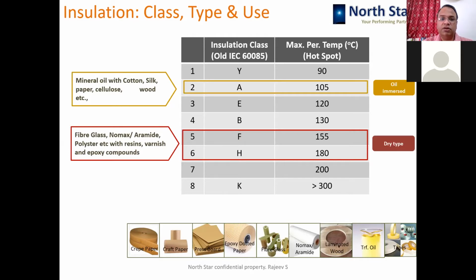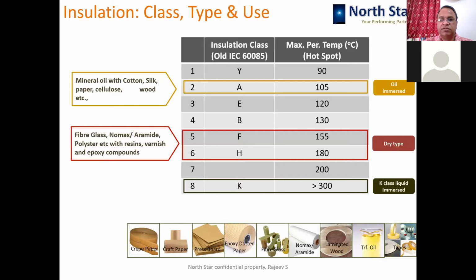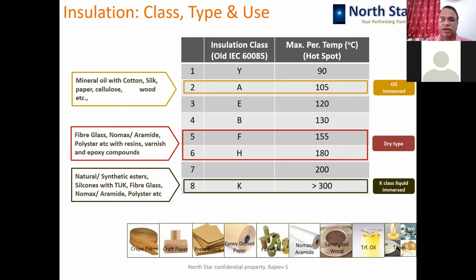These transformers use non-hygroscopic insulating materials, synthetic materials like Nomex, aramid, polyester, along with different types of resins, varnishes, and epoxy compound. Then the third category is K-class liquid immersed insulation, that is natural and synthetic esters with solid material that can be non-hygroscopic, that is class A type, as well as non-hygroscopic class F and H type, as well as class A hygroscopic like cellulose-based material. So based on the insulation combination, we can achieve the maximum hotspot temperature with K-class insulating liquid higher than mineral oils, up to beyond 300 degrees centigrade also. So as far as temperature is concerned, K-class insulating liquids are the best insulating systems for transformers from a fire safety point of view and overloading point of view.